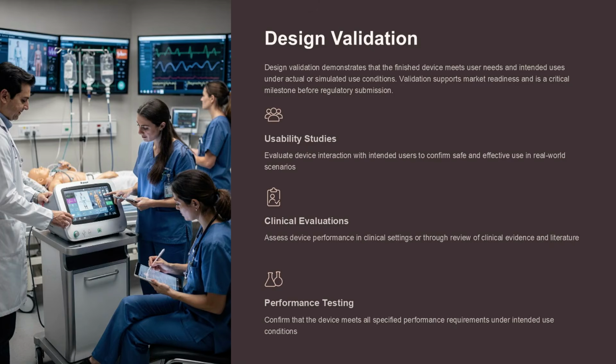Design validation demonstrates that the finished device meets user needs and intended uses under actual or simulated use conditions. Validation supports market readiness and is a critical milestone before regulatory submission. It involves evaluating device interaction with intended users to confirm safe and effective use in real-world scenarios, assessing device performance in clinical settings or through review of clinical evidence and literature, and confirming that the device meets all specified performance requirements under intended use conditions.